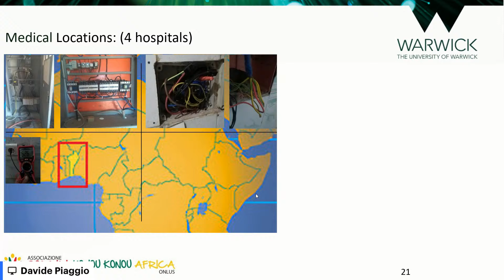These are some pictures taken of some of the power sockets in the hospitals, and what you can notice is the adapters usage. What we were measuring here was the voltage on the ground pin, the grounding I mentioned before, which is this middle pin here and which normally should be 0, if we lived in an ideal world. We don't live in an ideal world, so even if I were to measure it in my office, it would be a few volts, 3, 4, 5 volts. But here we're reading 84, 52, 94, 107. This voltage means that the system is not working properly, or because there is a use of adapters.